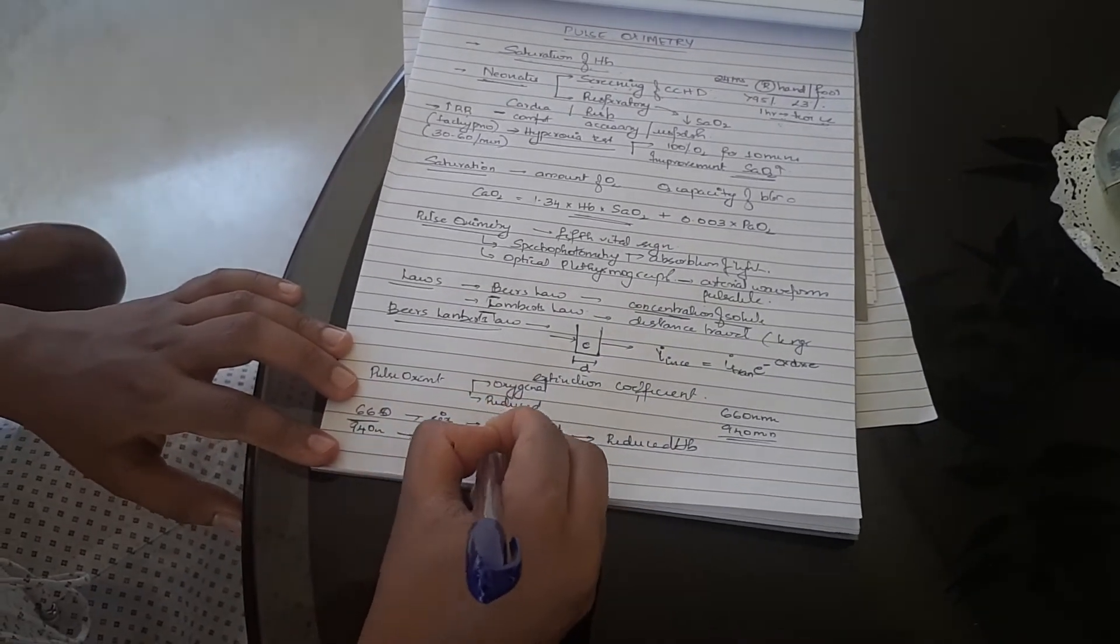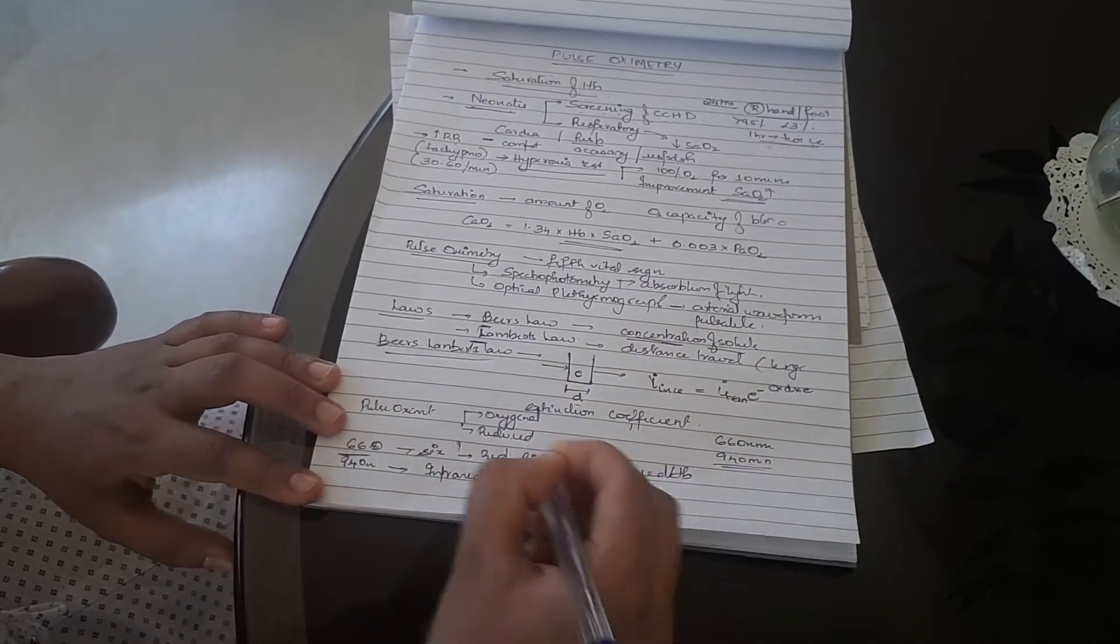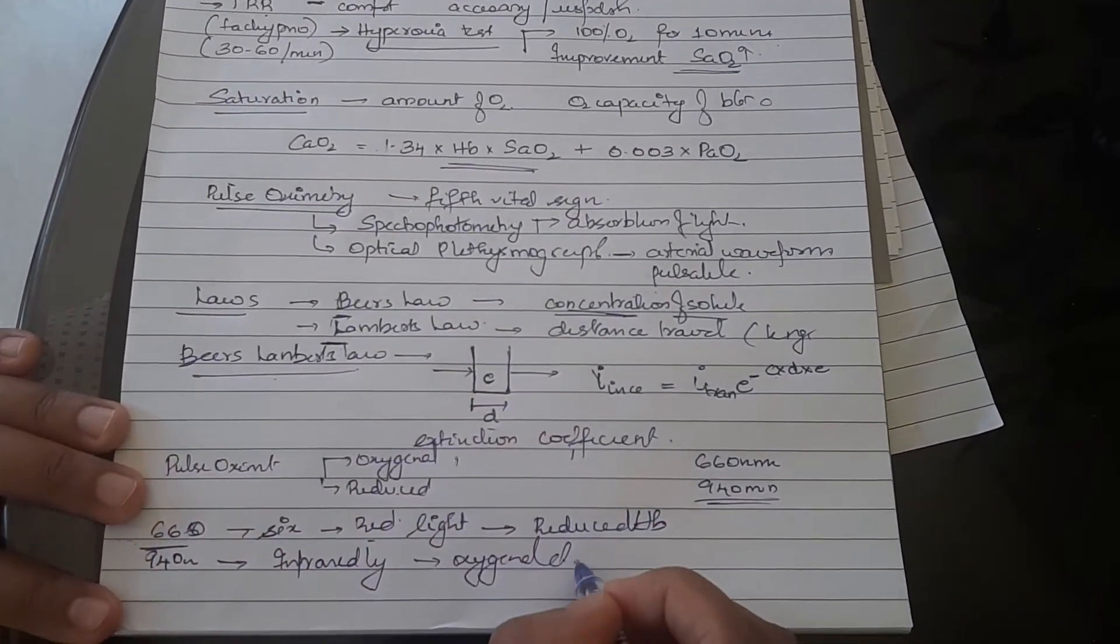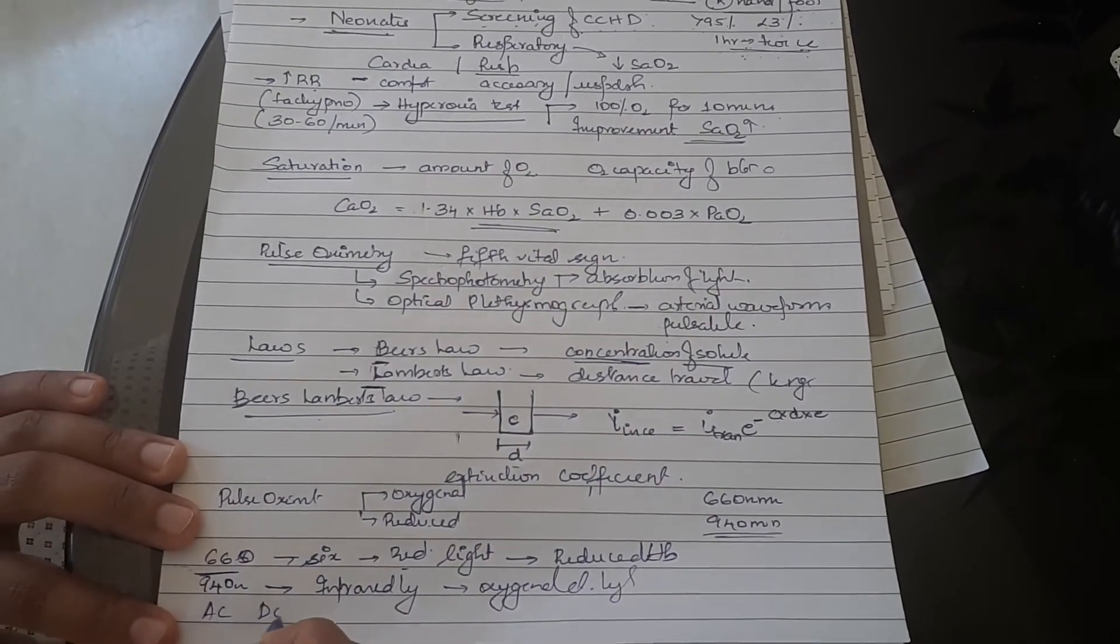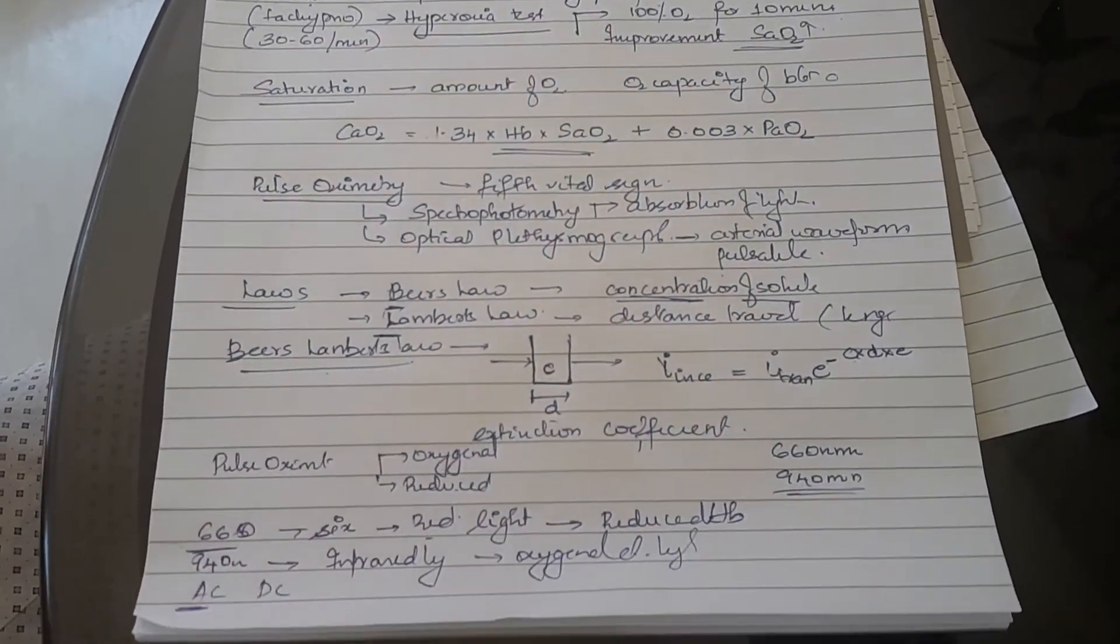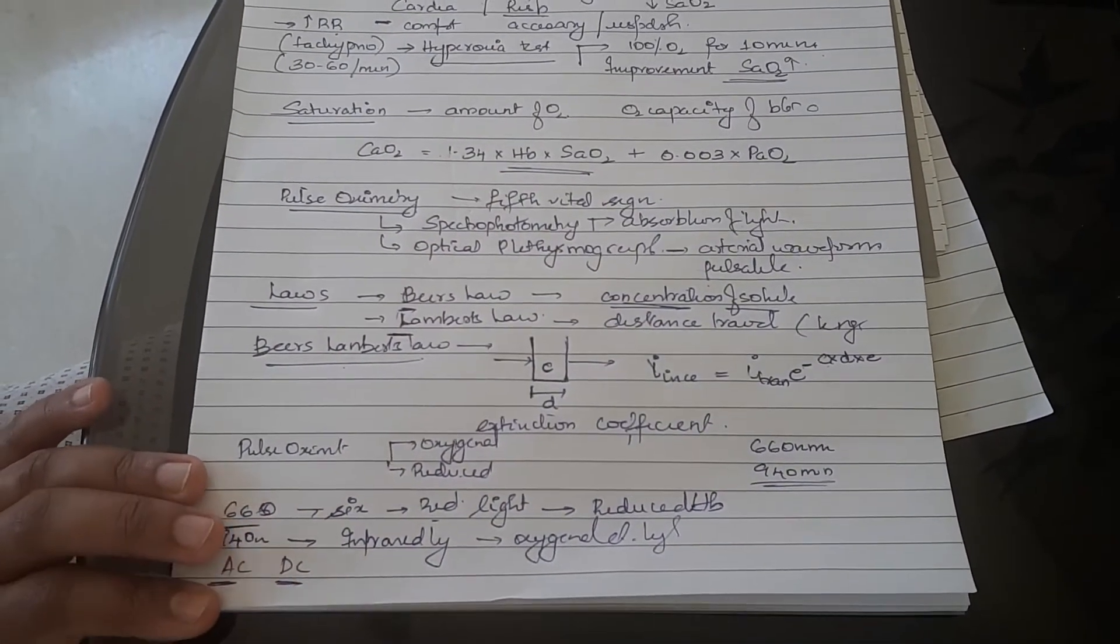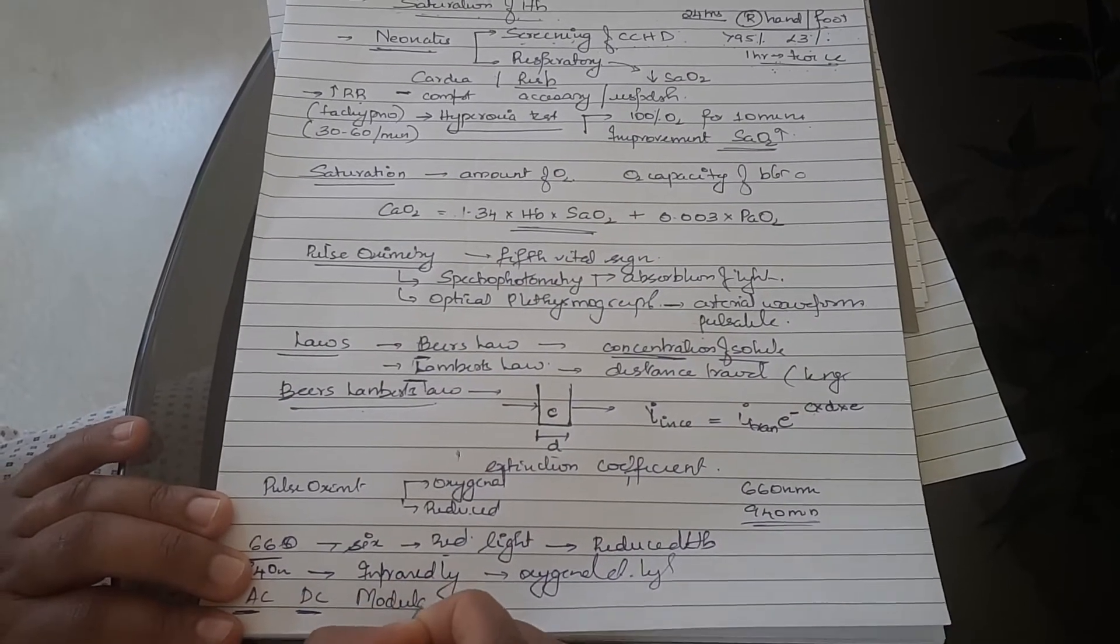Infrared light is for oxygenated hemoglobin. Based on how much of these two wavelengths are absorbed, a value will be obtained using alternating current and direct current. AC will be the pulsatile arterial waveform and DC will be the non-pulsatile part of the tissues. A ratio called the modulation ratio will be obtained.